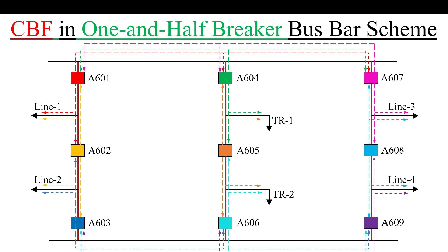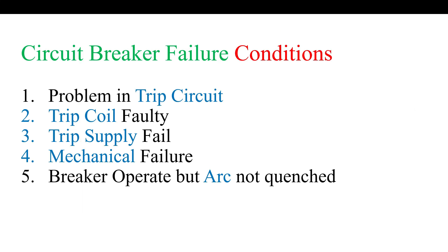There are a total of five circuit breaker failure conditions. The first condition is a problem in the trip circuit — if the relay gave a trip command but due to a problem in the trip circuit the circuit breaker does not operate, this is circuit breaker failure. The CBF protection relay will then operate and isolate the circuit breaker.